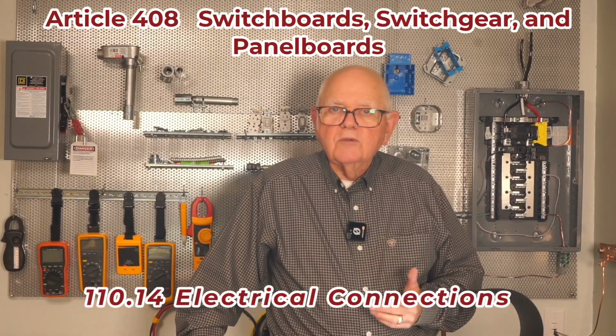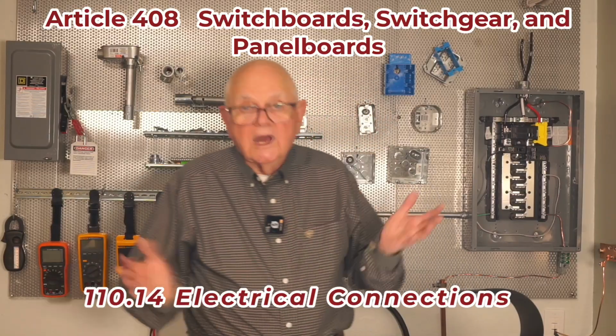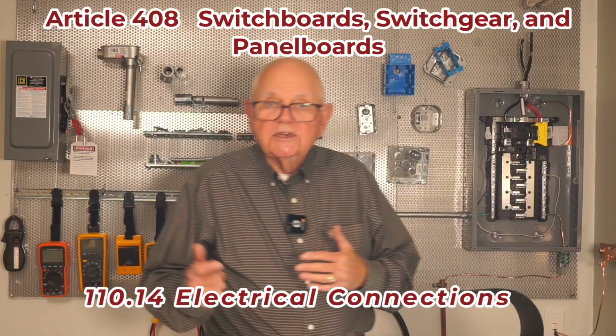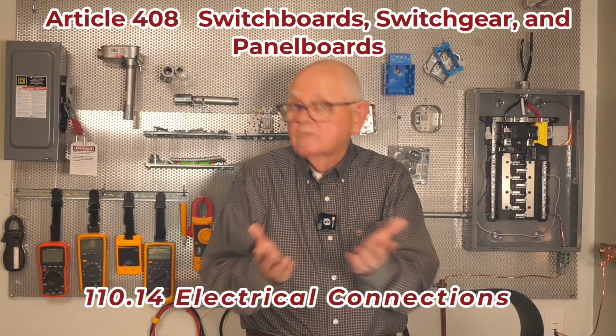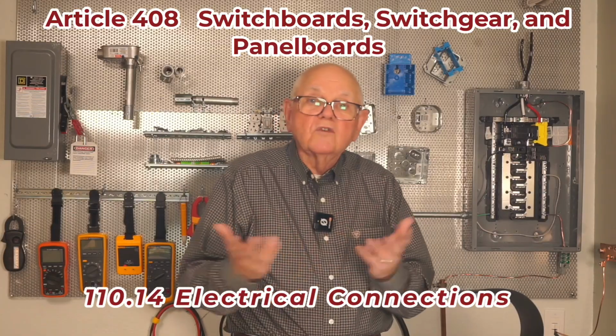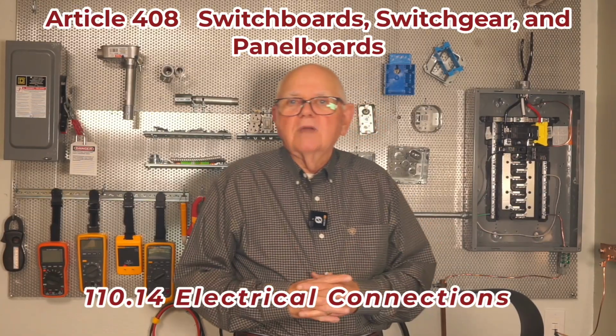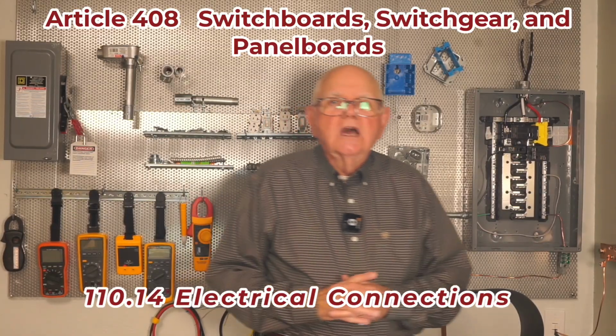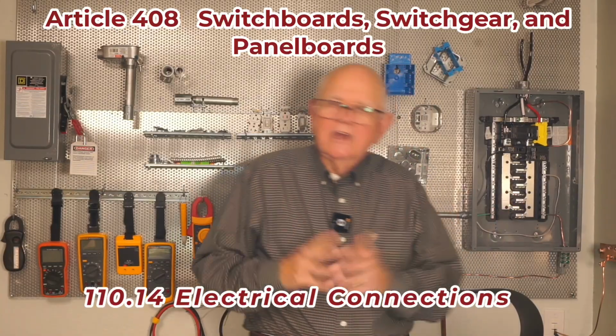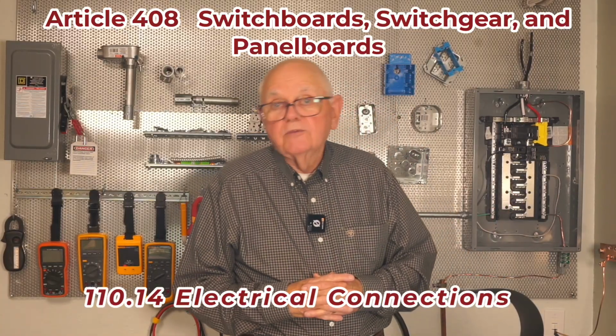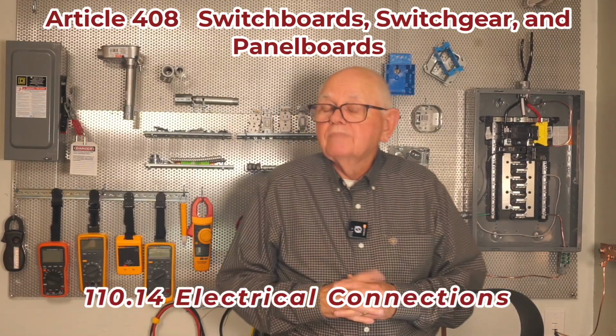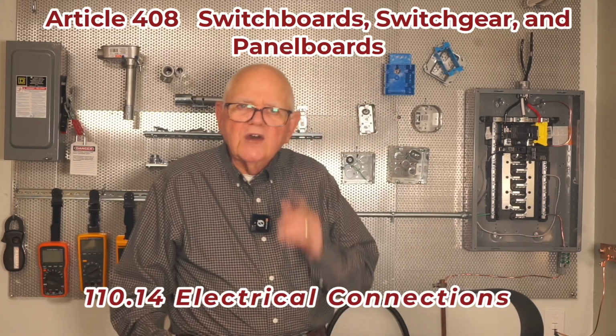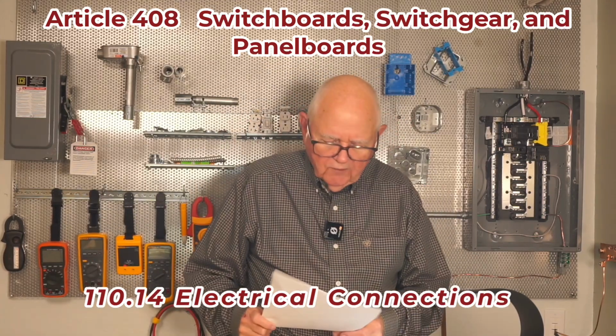Follow those requirements. If I don't apply enough torque, I obviously have a problem. Something could come loose, or I could have an overheating problem from too much resistance. If I over torque, I create additional problems as well. Conductors can loosen underneath a terminal screw, and once again, the ultimate thing to go wrong would be to have a fire, and we certainly don't want that. So follow your torque requirements in 110.14.